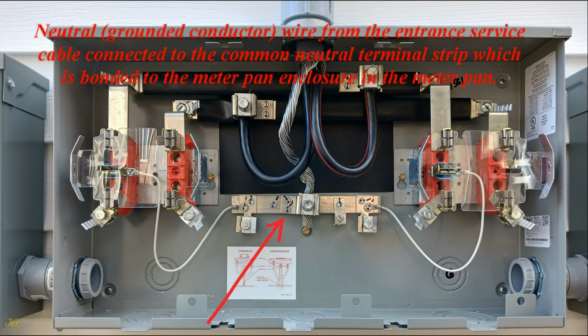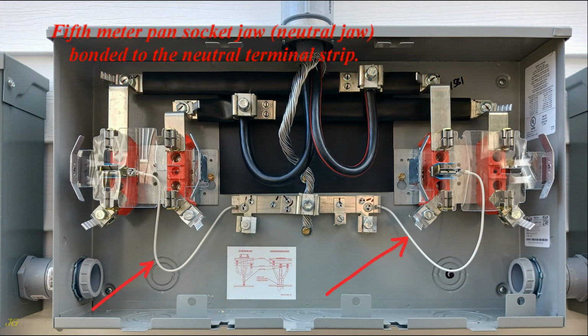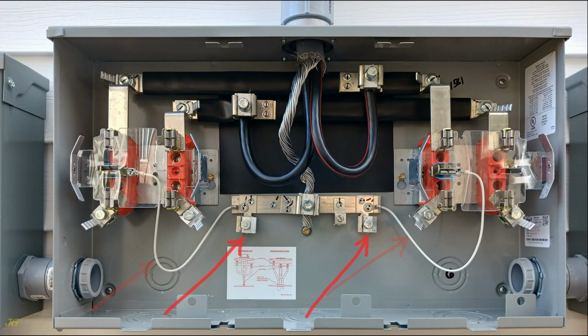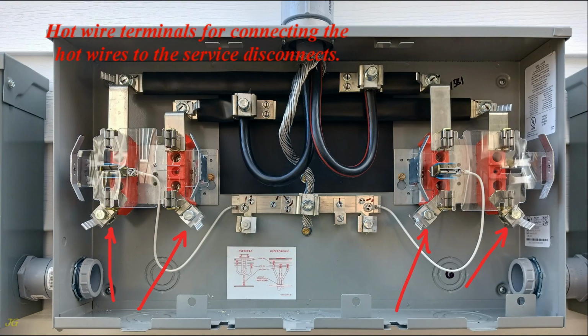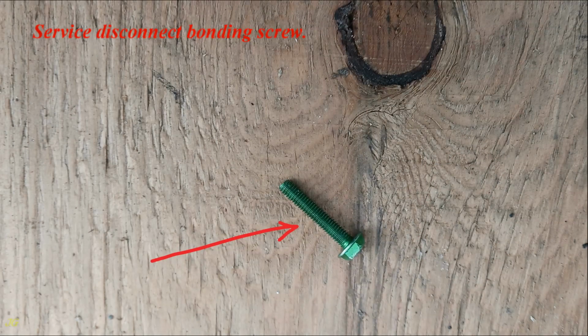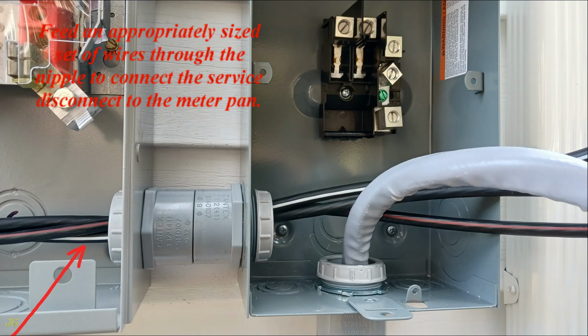Neutral, grounded conductor, wire from the service entrance cable connected to the common neutral terminal strip which is bonded to the meter pan enclosure in the meter pan. Fifth meter pan socket jaw, neutral jaw, bonded to the neutral terminal strip. Neutral wire terminals for connecting the neutral wire to the service disconnects. Hot wire terminals for connecting the hot wires to the service disconnects. Service disconnect bonding screw. Feed an appropriately sized set of wires through the nipple to connect the service disconnect to the meter pan.